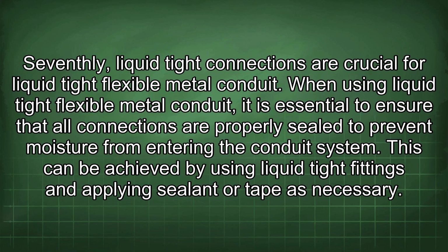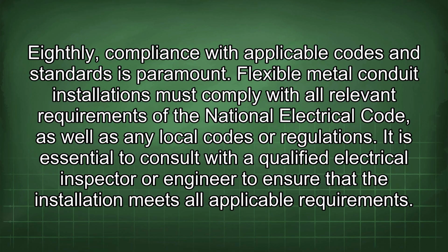When using liquid-tight flexible metal conduit, it is essential to ensure that all connections are properly sealed to prevent moisture from entering the conduit system. This can be achieved by using liquid-tight fittings and applying sealant or tape as necessary. Eighthly, compliance with applicable codes and standards is paramount.